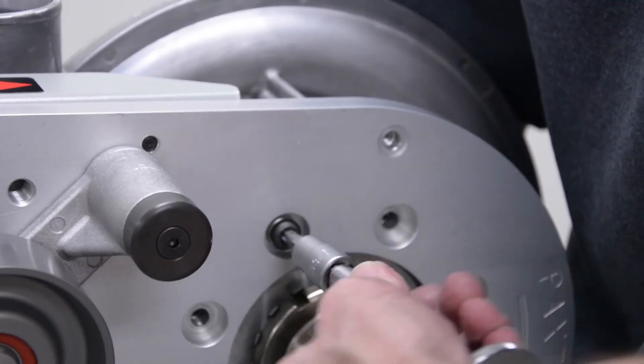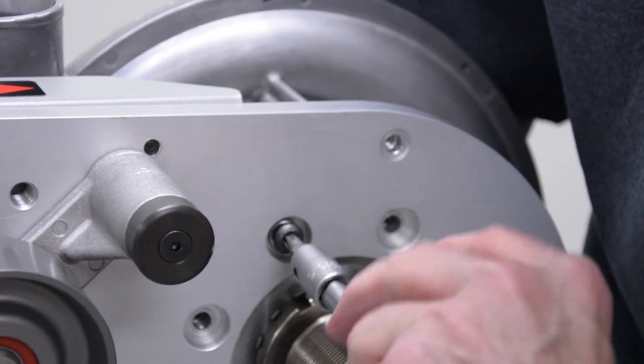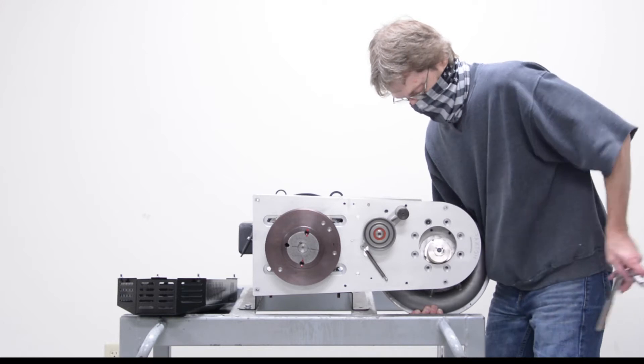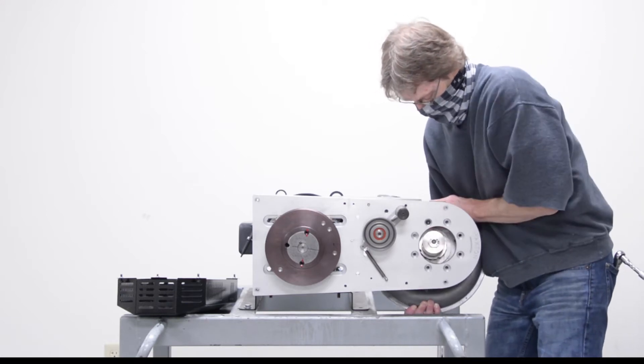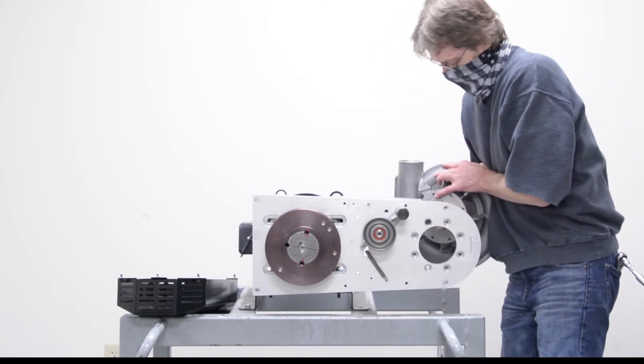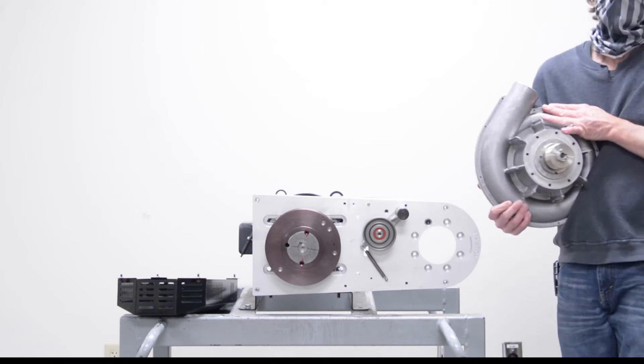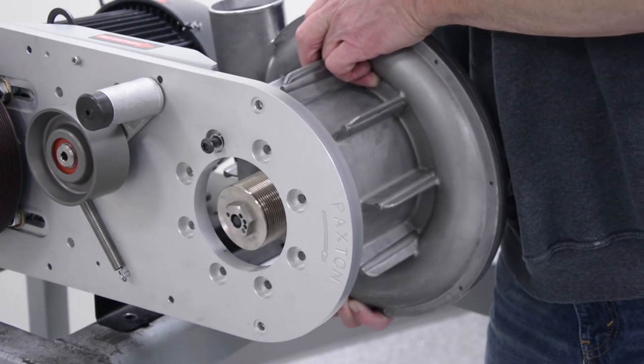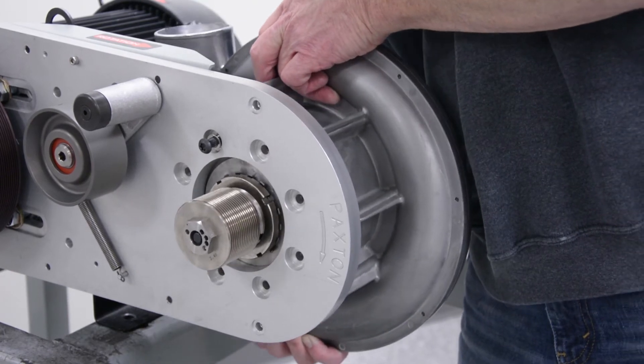Remove the eight retaining bolts holding on the blower hood. Be careful not to drop the hood when you remove the last bolt. Install the replacement hood, making note of the discharge orientation and ensuring that it's in the same rotation as the original blower hood.